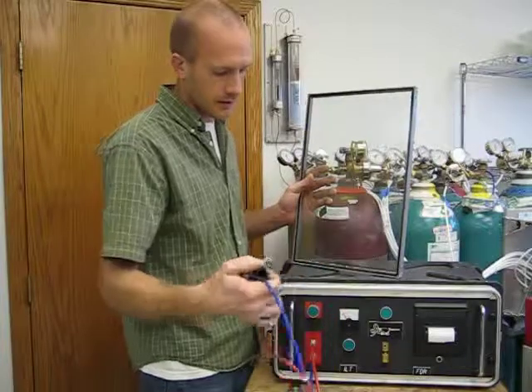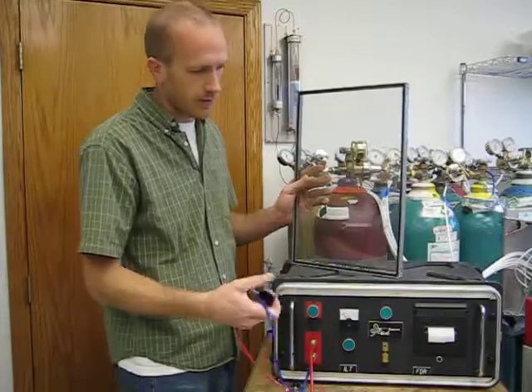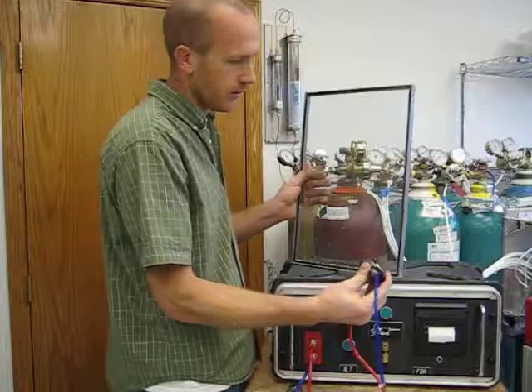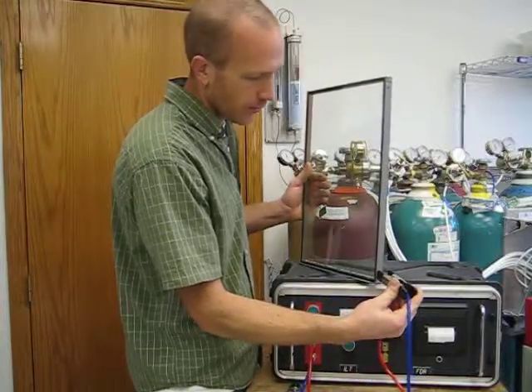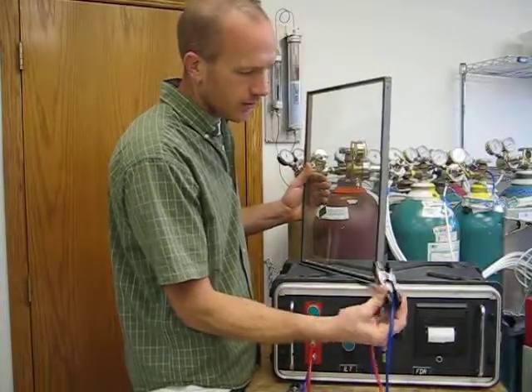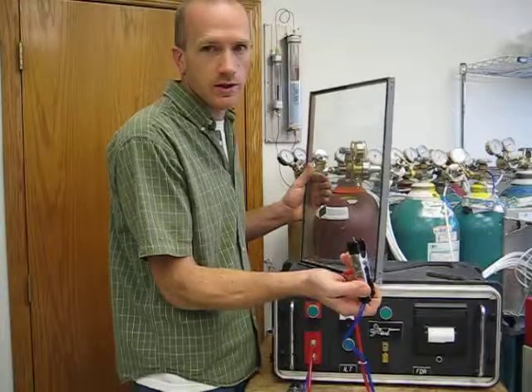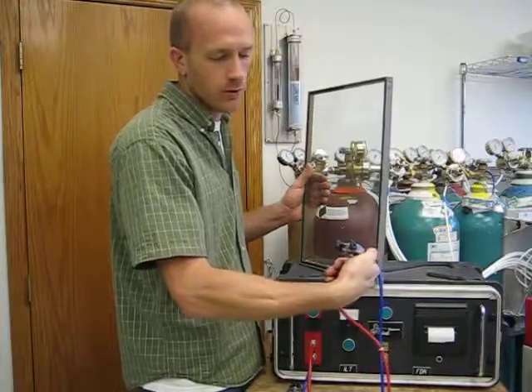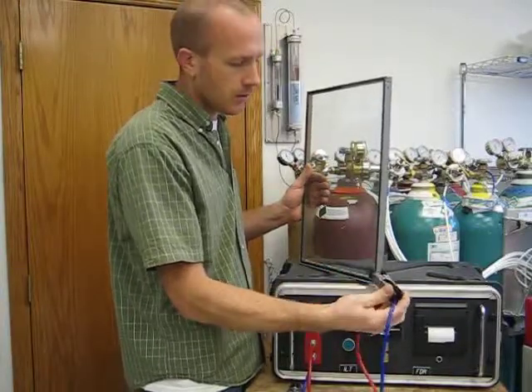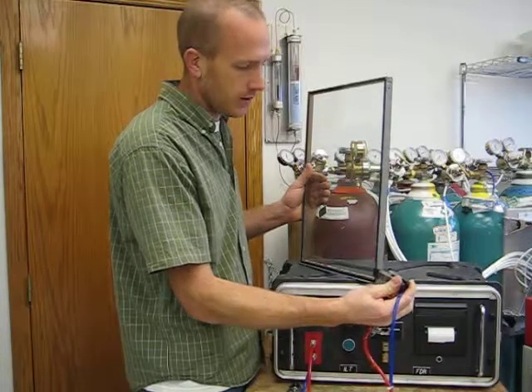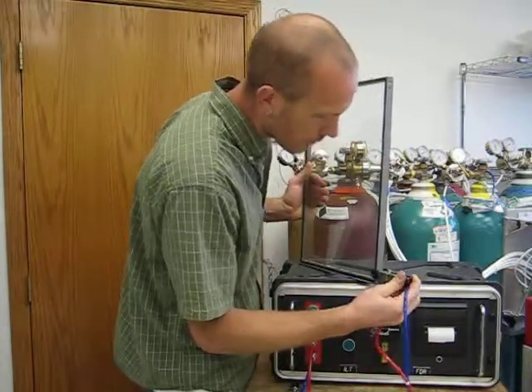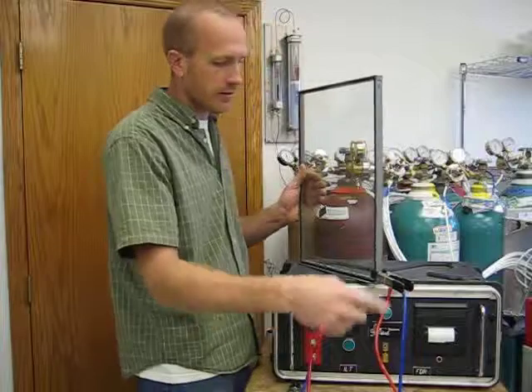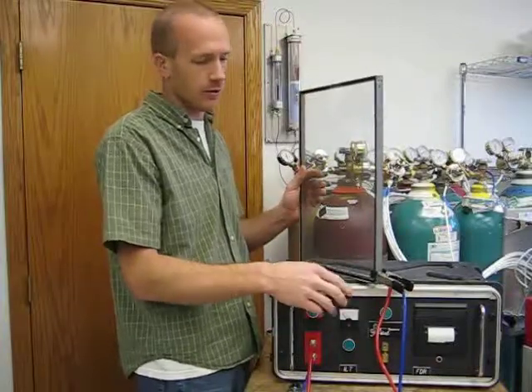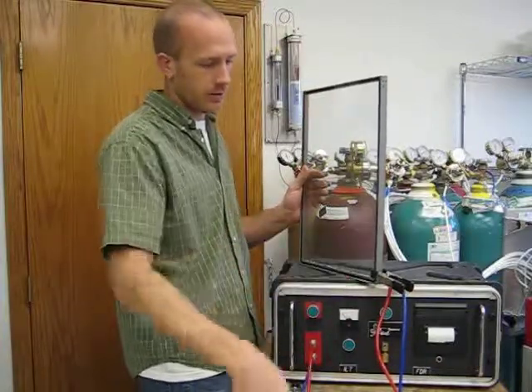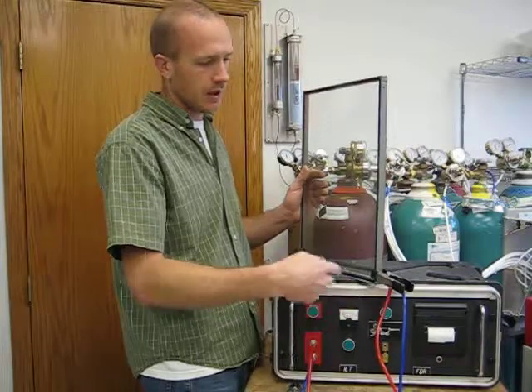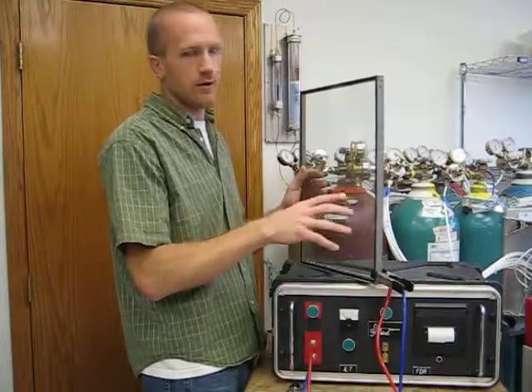a lance that's connected to the tester will be inserted through the gas filling holes or through the corner key or whatever. This lance is a combination lance. There's actually two, one inside the other. One sucks the gas out of the unit. The other puts the gas back in. So it's just a closed loop. It's pulled out of the window, runs through the machine, and then is put back into the window again.